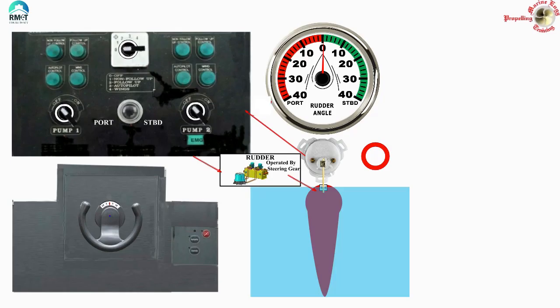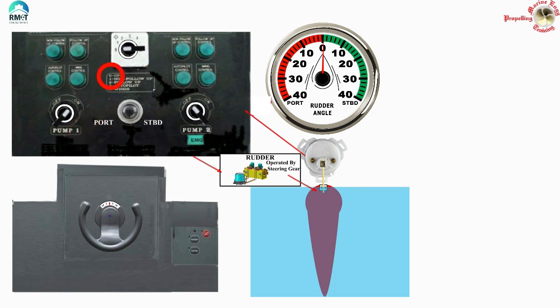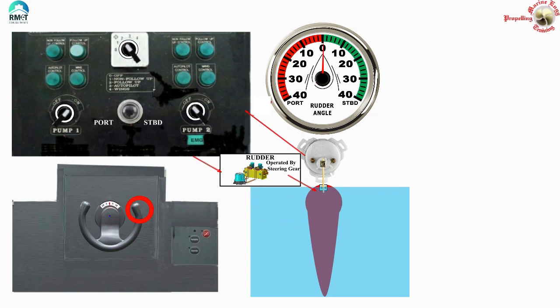Now let me put pump number one on. The moment I put the pump on it's ready, and now I need to choose follow-up, non-follow-up, or autopilot. I am going to choose follow-up - position 2. The selector switch is now on position 2, and the follow-up light is lit up. This means autopilot is not going to control the rudder; my wheel is going to control the rudder. Let me start with starboard 5 - the rudder has responded and gone to starboard 5, and the rudder angle indicator is also showing starboard 5.